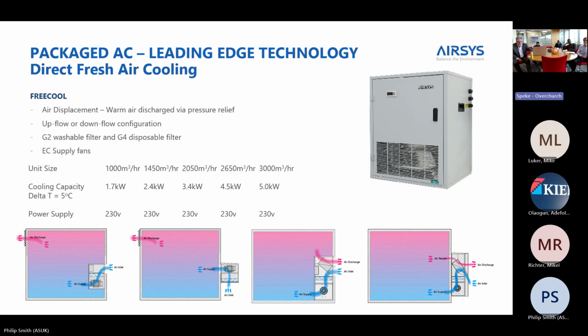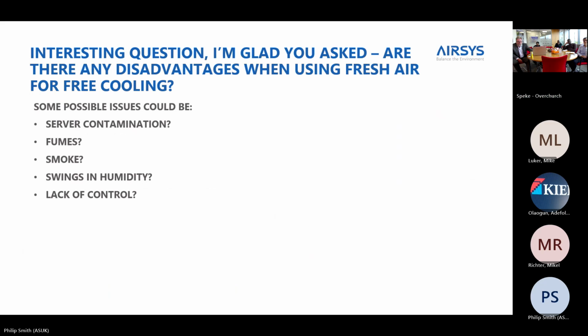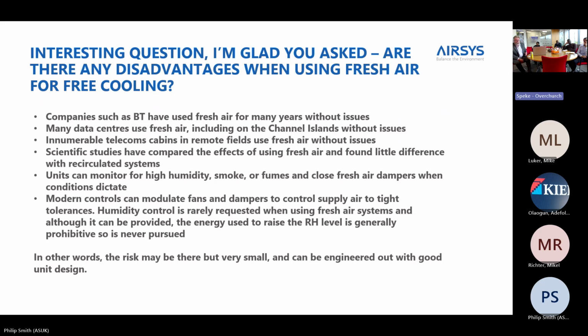And they go down to a very small size, up to 20 or 40 kilowatts. Yes. Are there any disadvantages when you're using fresh air, particularly fresh air for free cooling? A lot of people say that you bring in contamination, fumes, smoke, humidity, and do you get lack of control? Now, the honest answer to that is, if you look at people like BT and others, they have used fresh air for decades with very little effect on the IT equipment that they use. We've got installations in the Channel Islands where you couldn't get much worse conditions, and they have no issues.